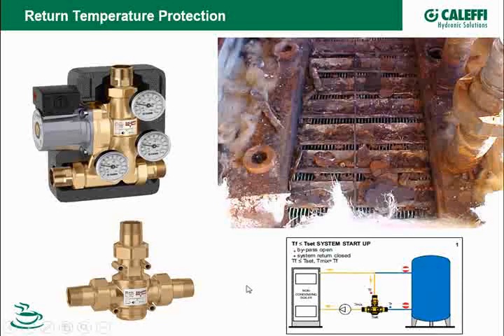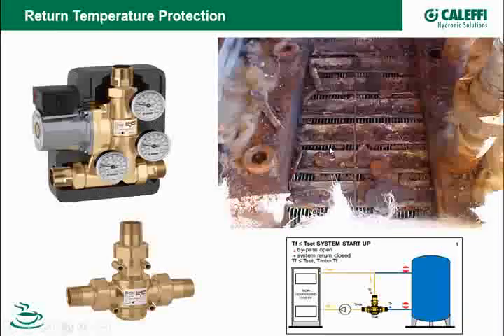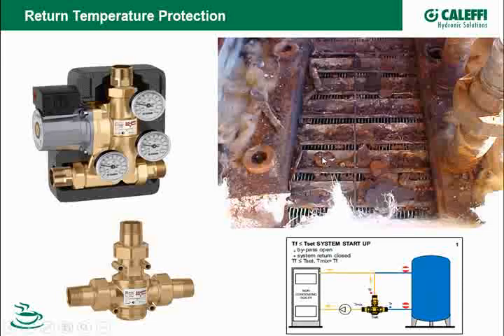If you're going to be working with radiant systems, especially radiant systems in concrete slabs, they've got the ability to keep a boiler down in the condensing mode for extended run periods, and that's going to be a problem. Unless the boiler is specifically designed for that, like a condensing boiler that likes to have cold return temperatures and scrub some of that additional heat out of the flue stream, you want to have some sort of protection device.